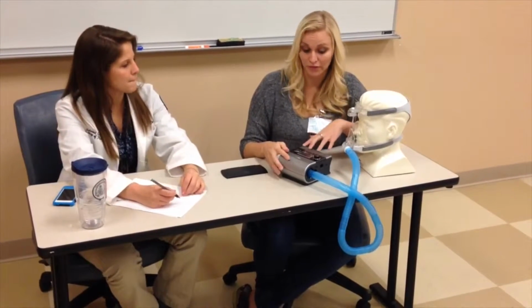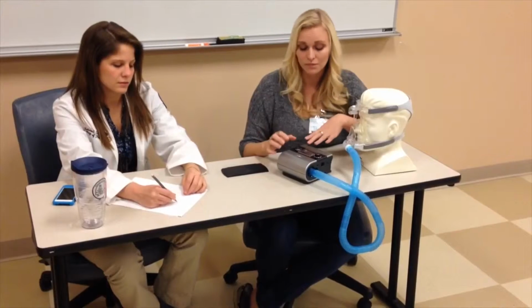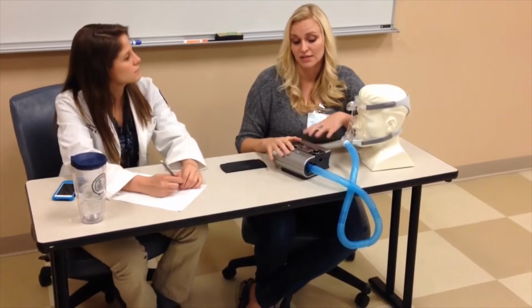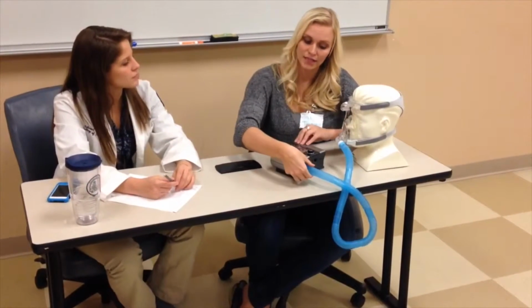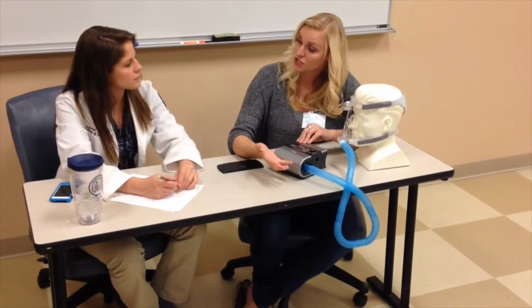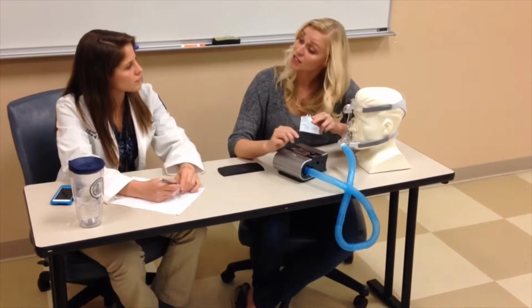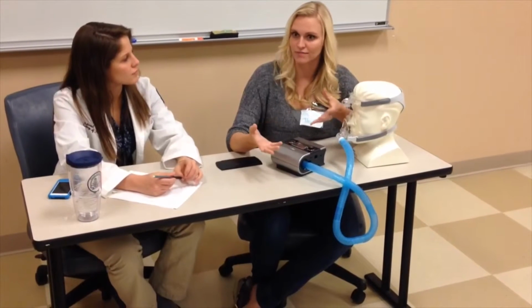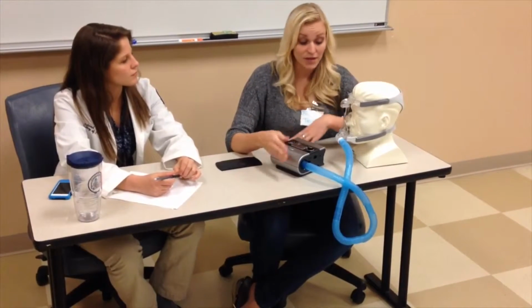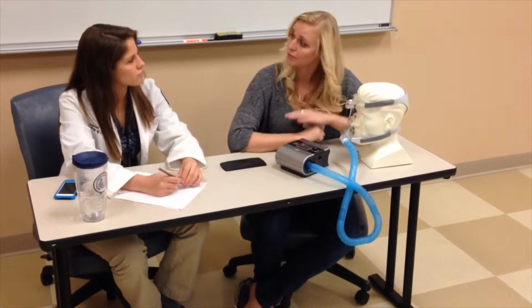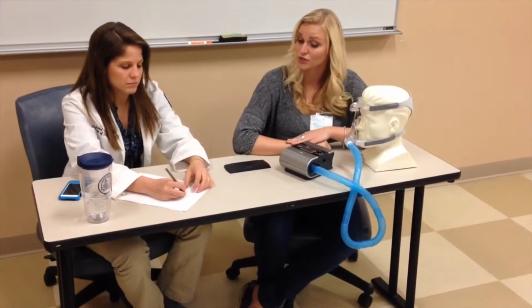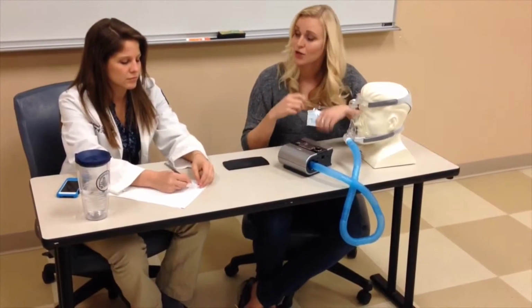Because that cannula, how it goes around your nose, around your ears, it's going to disrupt the seal. So you're not going to get the full pressure that the patient needs in order to prevent their airway from collapsing. An easy thing to do is they have adapters that you can plug either right here or into the humidification chamber that you can actually attach the oxygen to from the patient's oxygen concentrator at home. So that way they're getting their oxygen all throughout the night and they don't have to worry about it.